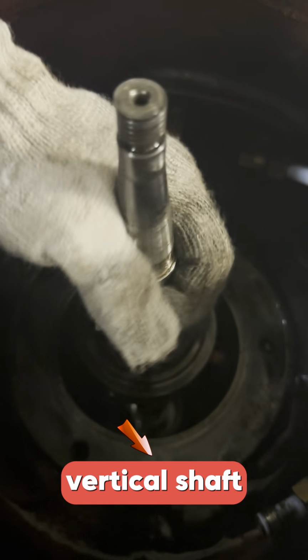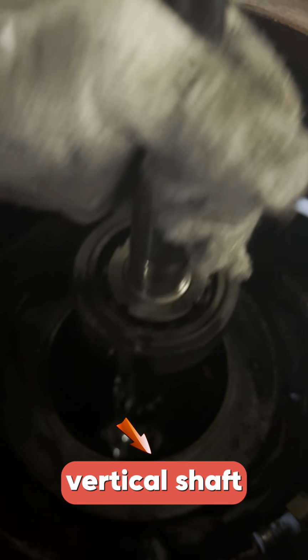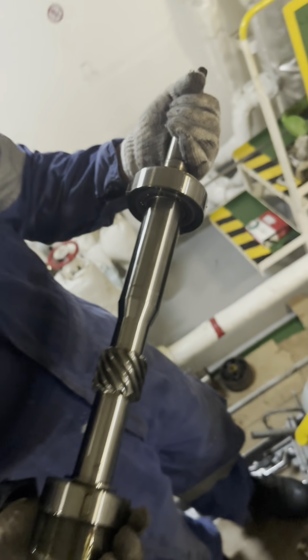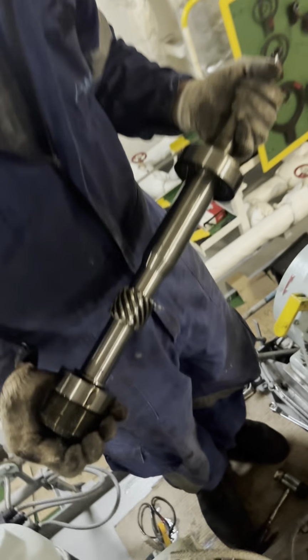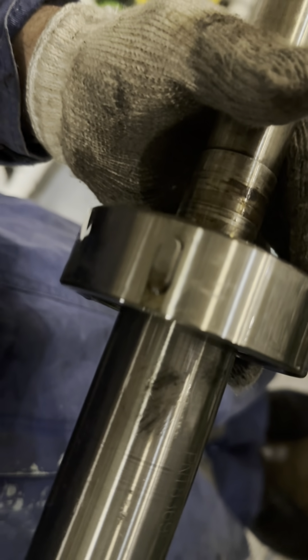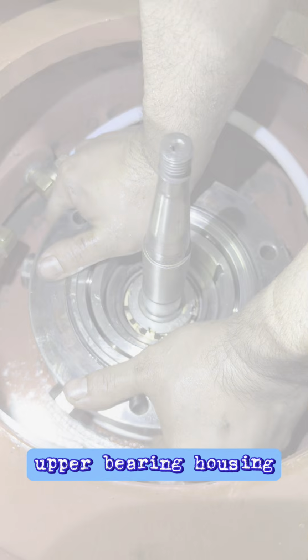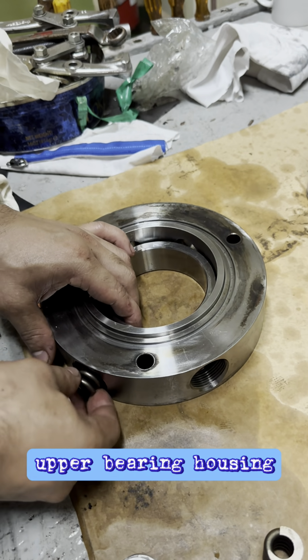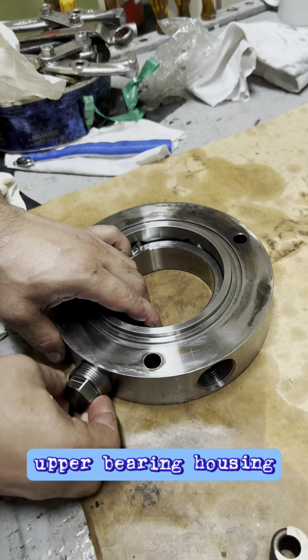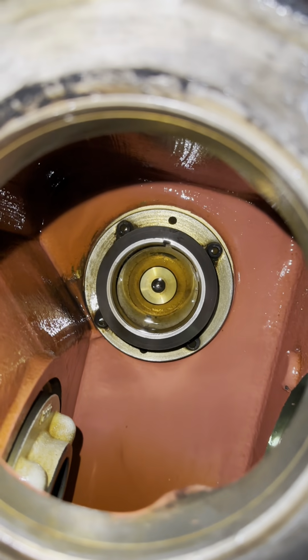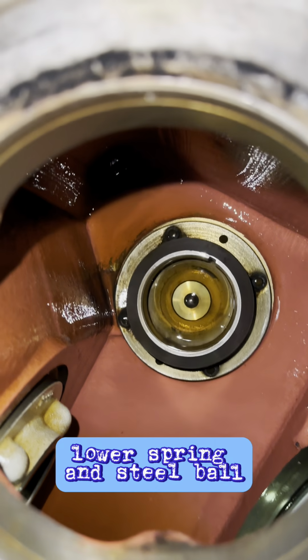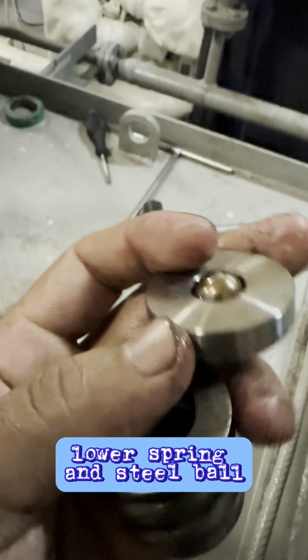The vertical shaft. The revolution speed of the horizontal shaft is increased by the vertical shaft pinion gear, and the vertical shaft rotates the bowl mounted on its top. The vertical shaft and bowl are supported by the upper springs and leaf spring radially incorporated at 6 points on the upper bearing section, and lower spring in the lower bearing section so that they can stably rotate.